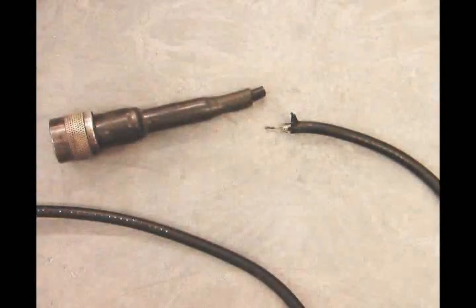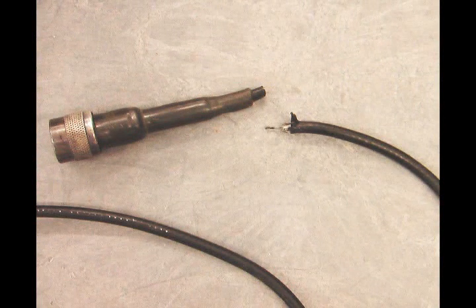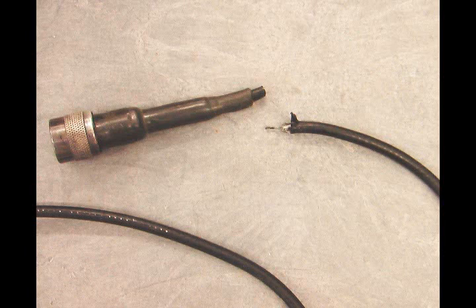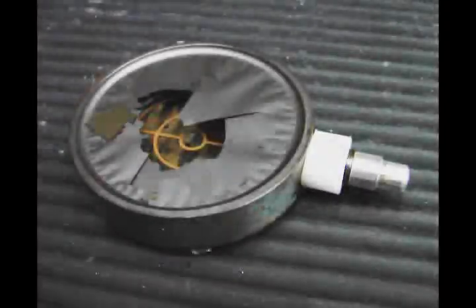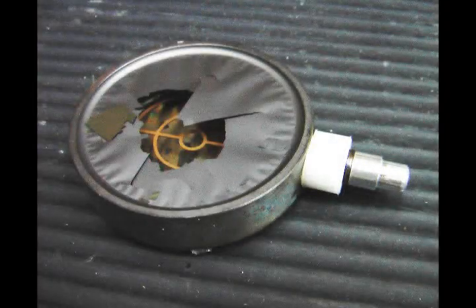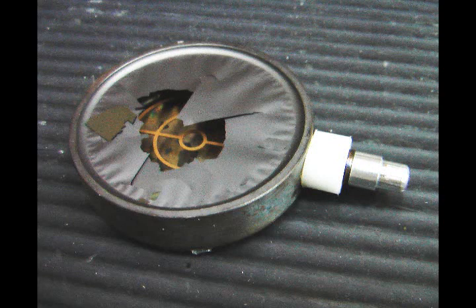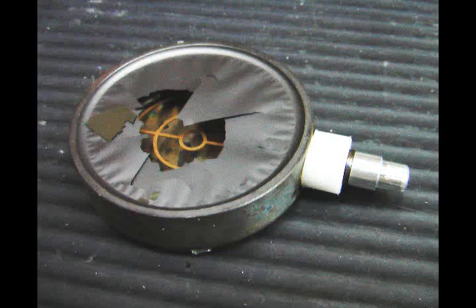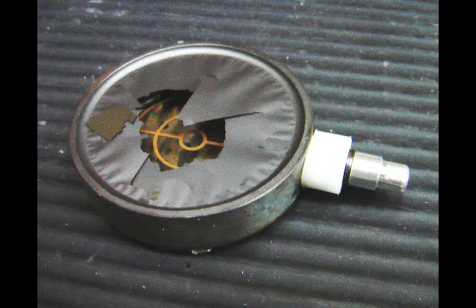The next problem, noisy or upscale readings, can be caused by a noisy cable or breakdown of insulation within the cable. Detect this problem by replacing cables or swapping cables from another instrument. Replacement of the defective cable is necessary. Detector breakage is another frequently seen problem. The Model 44-9's window is very thin and can be easily punctured by anything that sticks through the protective screen, even a dry blade of grass.